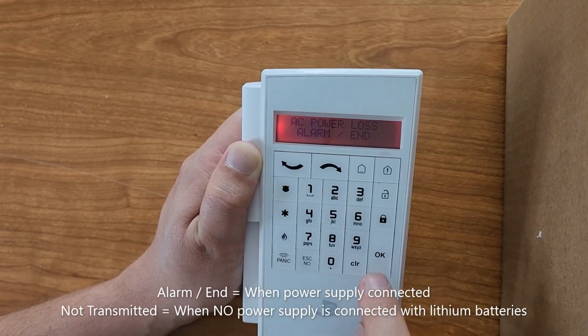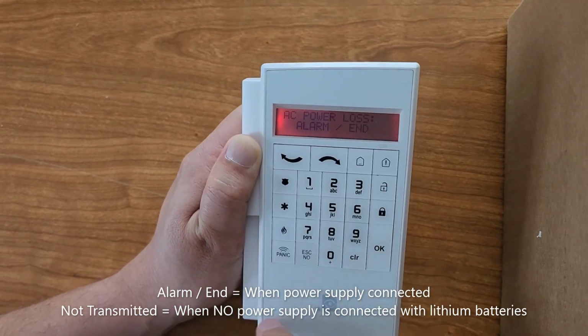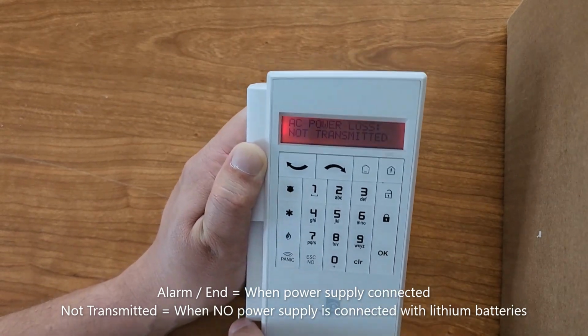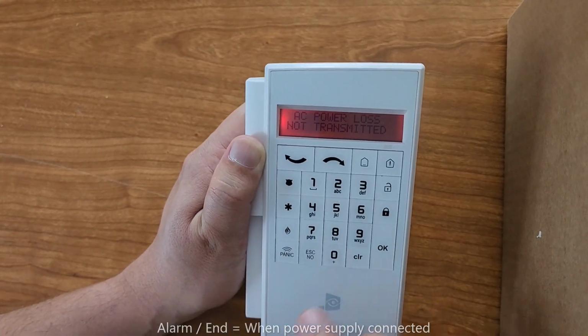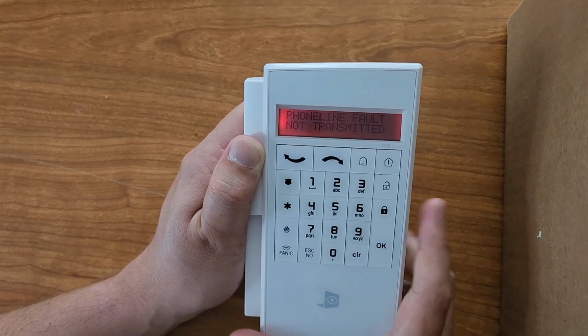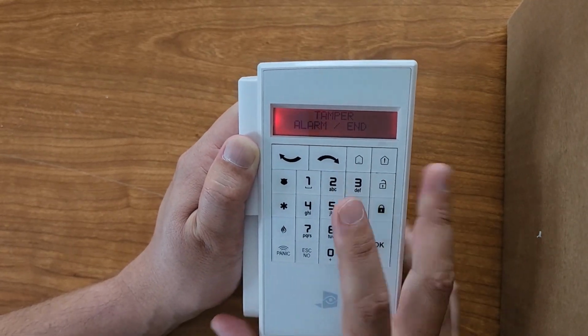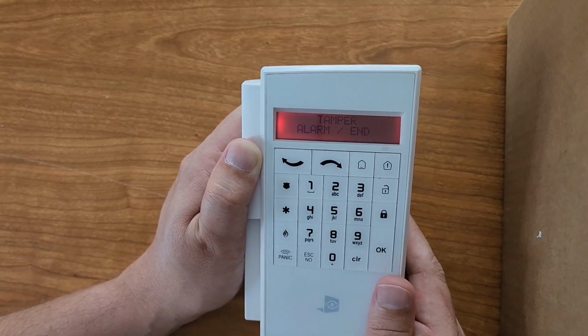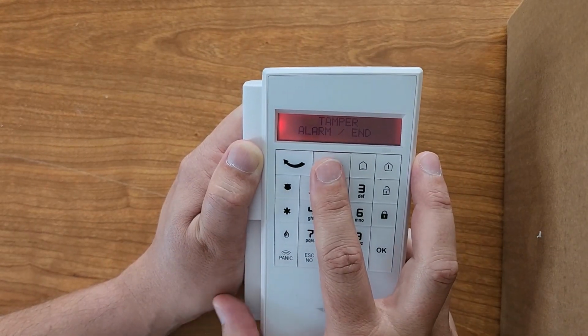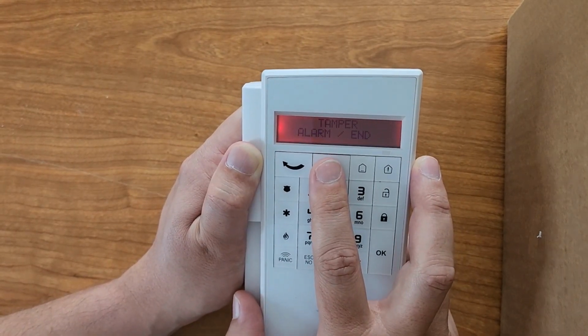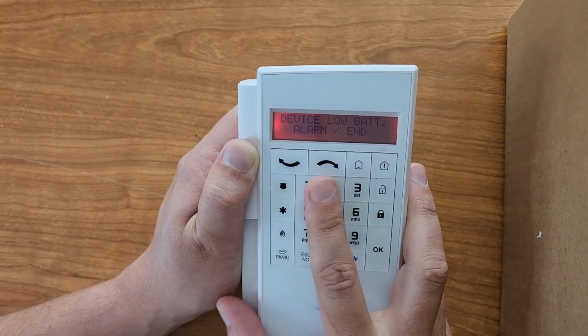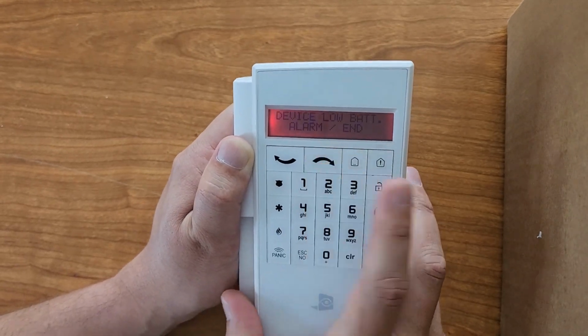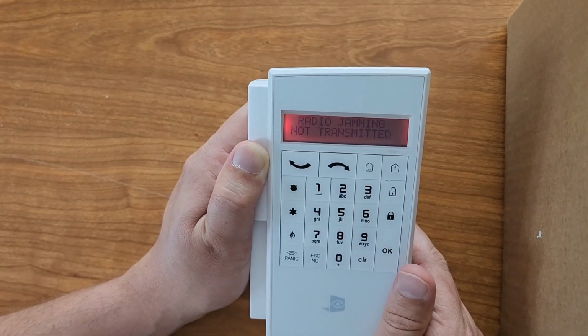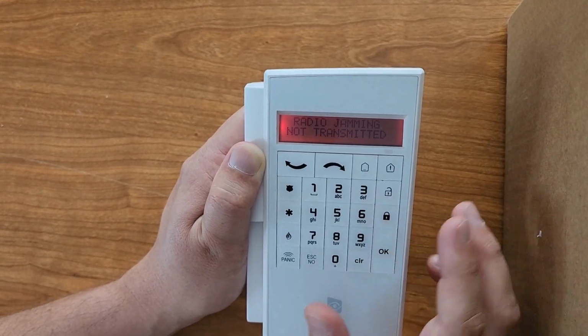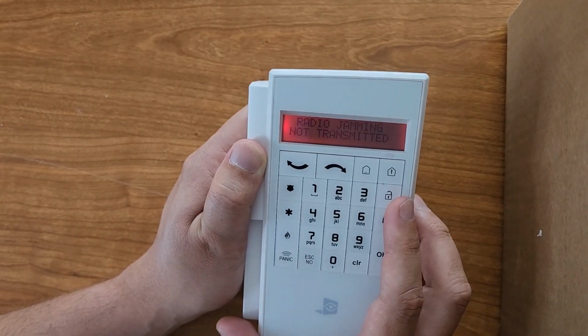Right, lithium one in my case will go to not transmitted, so I do not want an AC fail as no AC is connected. Next one, phone line fault, we don't use phone lines. Tamper, alarm/end, so you want to leave that, so if something tampers, you want to get the signal, and if it closes, you get the restoral. Your device low batteries will stay alarm/end. Radio jamming is up to your own preference. If your company wants you to monitor radio jamming, you can enable it.